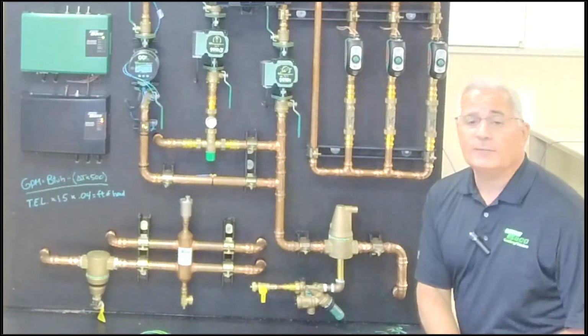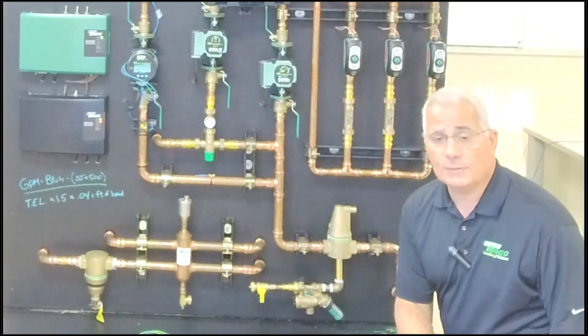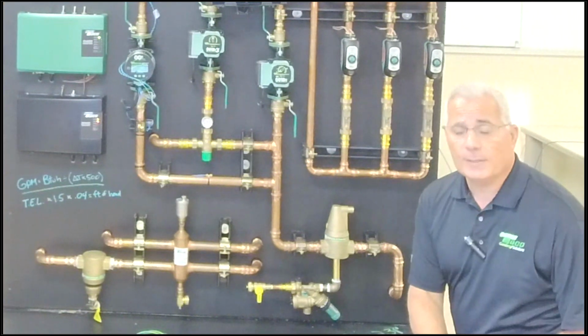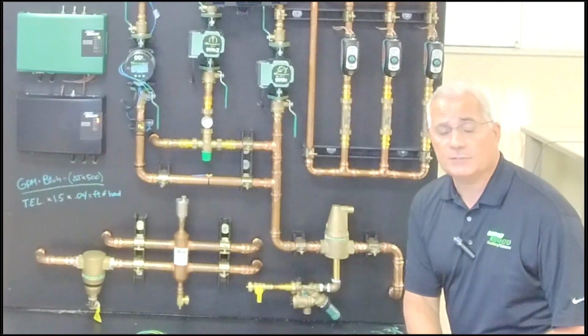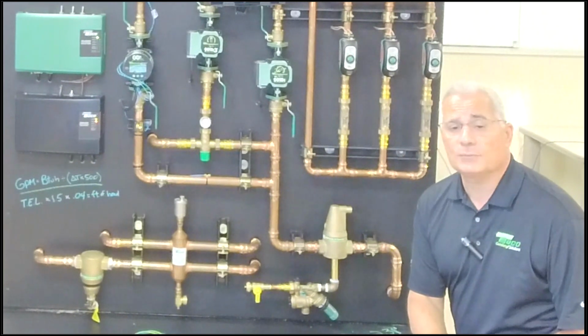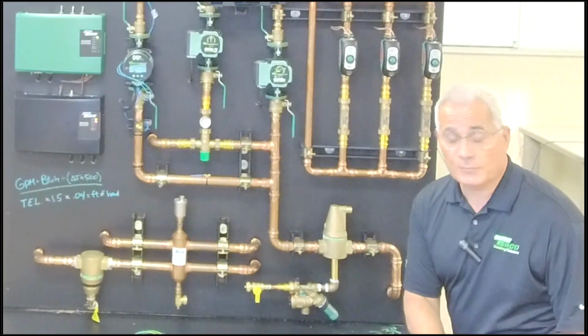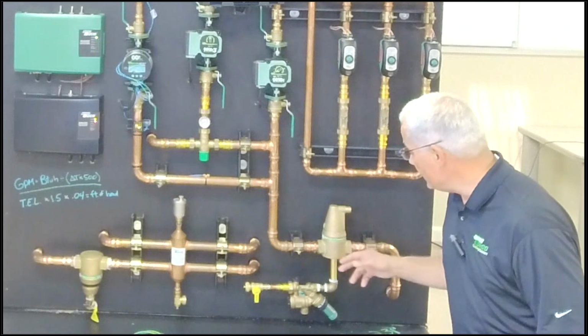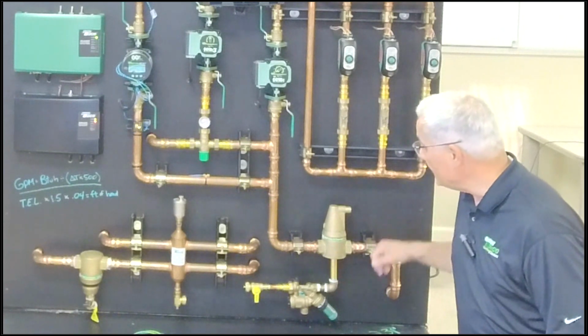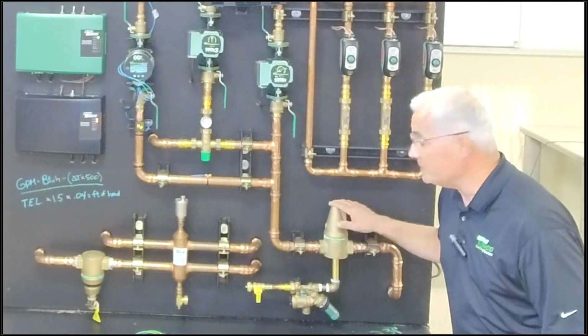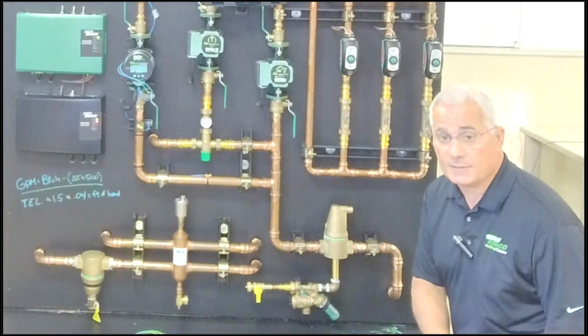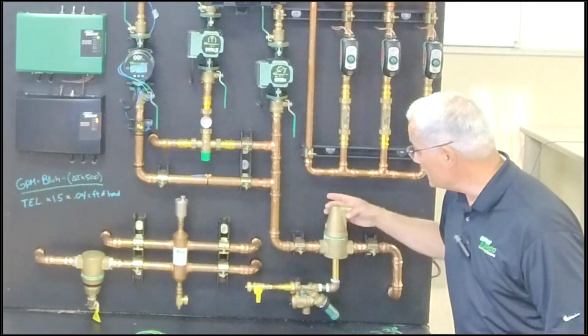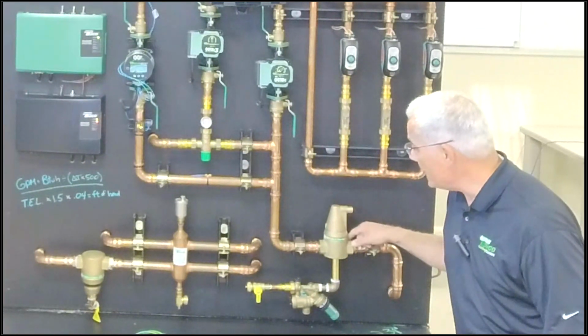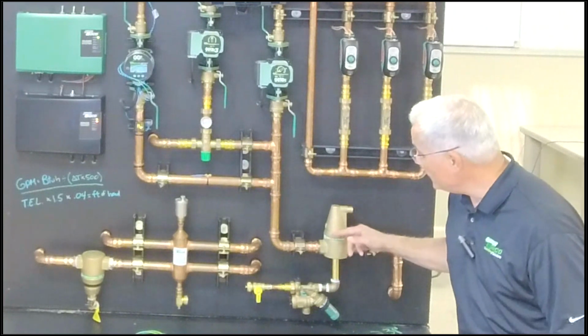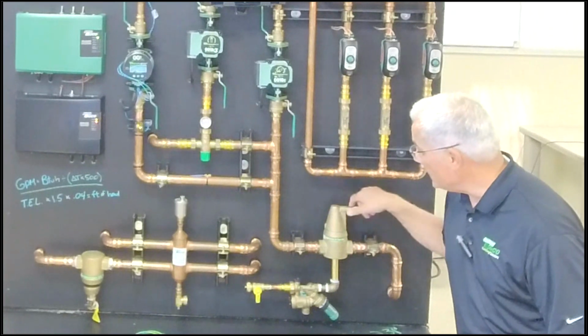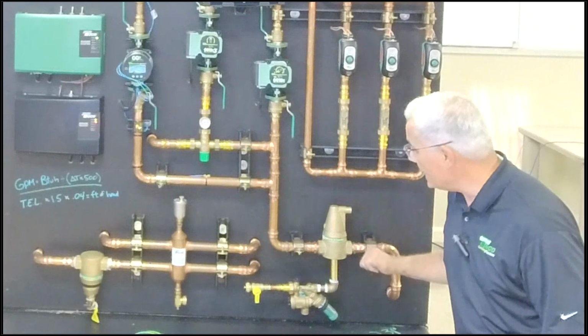If you've been to any of our other webinars in the past, you know that when we use an air scoop, we need at least 18 inches of straight pipe in front of that air scoop in order for it to work. With an air separator, we don't have to worry about that, and this will scrub out the air bubbles even as we are filling the system. You see the design here, it's a cone shape on the top, as opposed to my competitors that go straight up with a round shape and flat to the top.